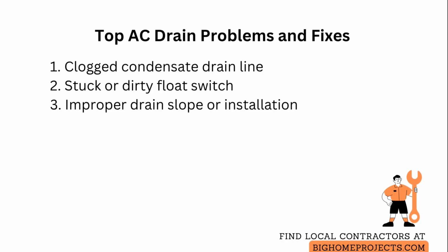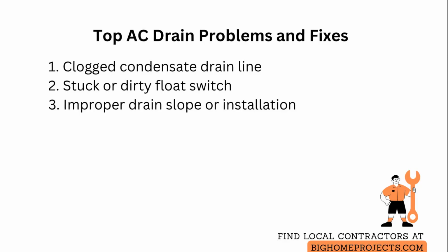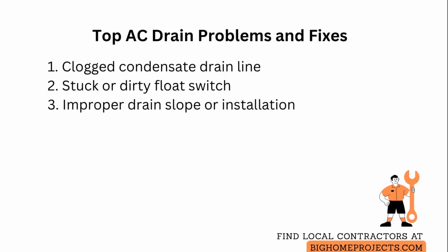Third, improper installation or lack of slope leads to standing water and repeated trips. Reroute or shorten the line to establish consistent downward pitch and add or service a condensate pump for units above the drain location.